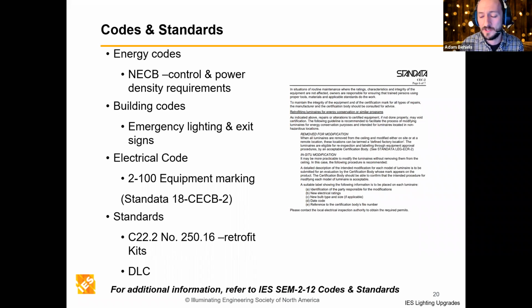Any additional information - there's also an IES standard on codes and standards itself, it's SEM 212. Keep in mind that may be very United States centric, so it's best to consult your AHJ. This is not an exhaustive list, so check what further codes may be applicable. Like just yesterday, I found out that in Calgary, the minimum parking lot lighting target is about 50 lux, which is 5 times what IES recommends. So there are some interesting things like that you can find out in local bylaws.